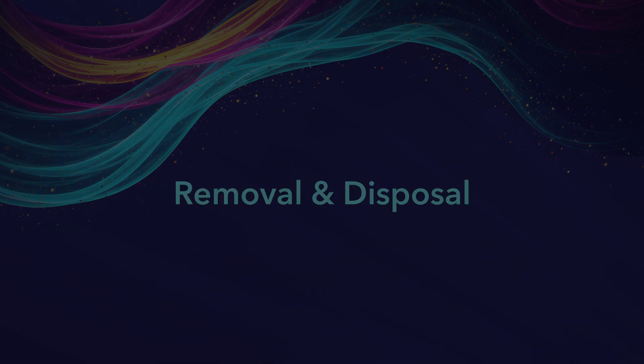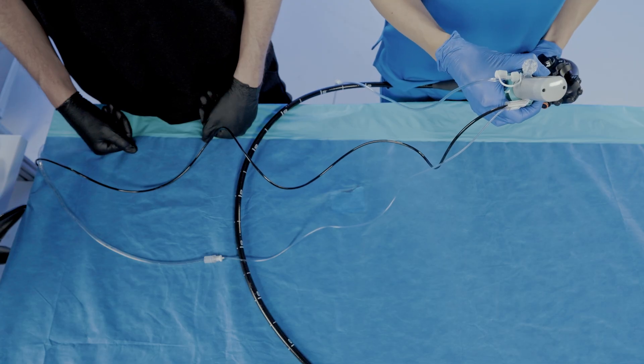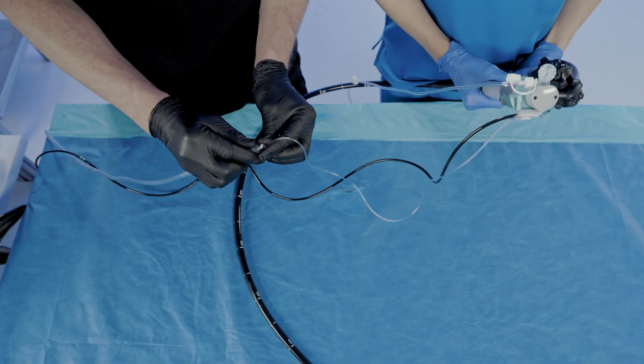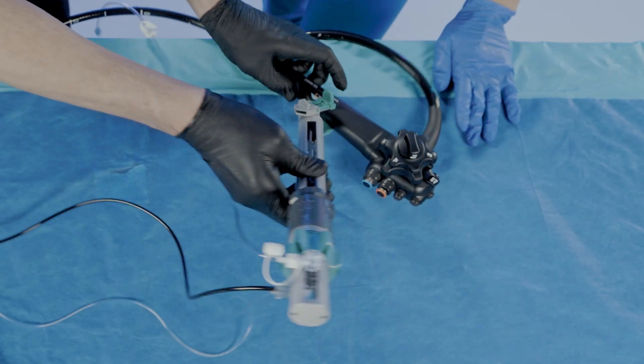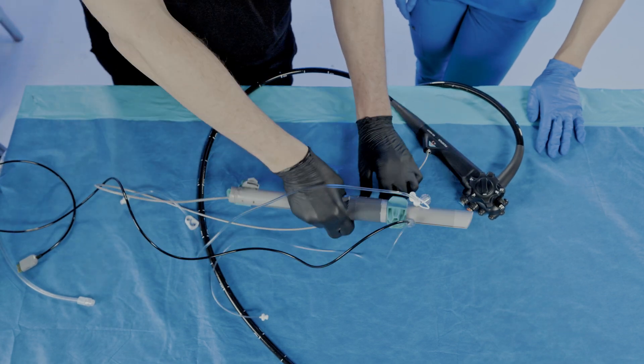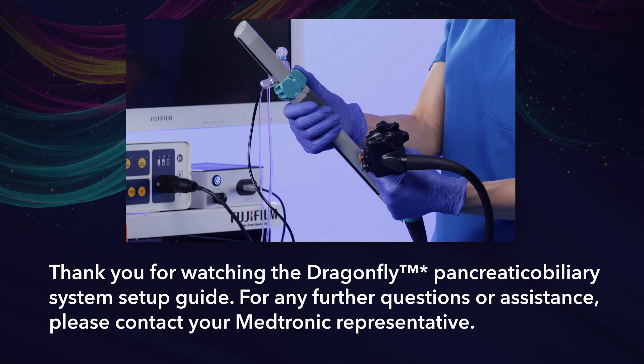Removal and Disposal. To remove the Dragonfly system from the scope, ensure the deflection knobs and torque control knob are in neutral. Then retract the flexible shaft and remove the accessory. Detach the DPS from the duodenoscope by releasing the attachment strap. Disconnect any other tubing. Unplug the cable connector from the DDC and remove the DPS from the duodenoscope. Dispose of the device following biohazard protocols. Thank you for watching the Dragonfly pancreaticobiliary system setup guide. For any further questions or assistance, please contact your Medtronic representative.